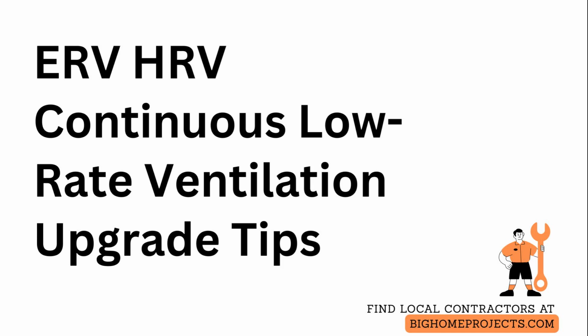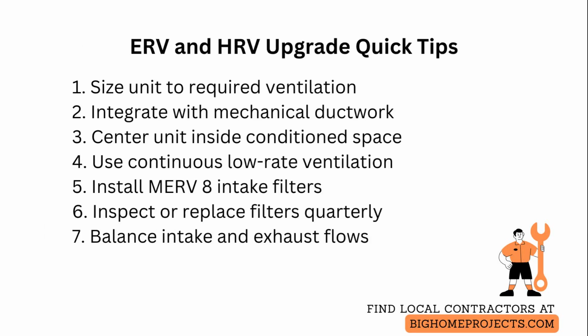Upgrading new home construction with an energy recovery ventilator or heat recovery ventilator is one of the most effective ways to improve indoor air quality while preserving energy. Choose an ERV or HRV sized to the home by calculating the continuous ventilation rate needed and matching the unit capacity to the total conditioned floor area and expected occupancy.